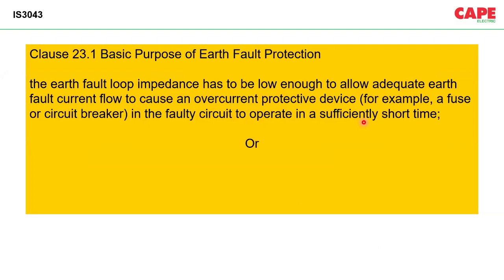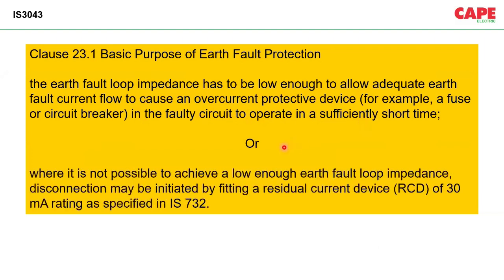If this is not happening, then where it is not possible to achieve a low enough earth fault loop impedance, disconnection may be initiated by fitting a residual current device RCD of 30 milliampere rating as specified in IS 732. So this particular clause explains very clearly that you have two options. One is your MCB should trip, but you have to have enough current to operate that particular MCB. In order to have enough current to operate that MCB, you have to have a very low earth fault loop impedance. And if this is not possible, you have to go to the second option. You install a 30 milliampere RCCB. This is the correct way of reading.